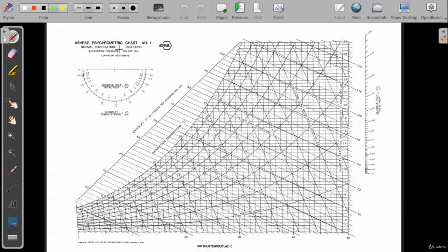Okay, so we shall use this psychrometric chart to help us retrieve the humidity ratio value. So the initial condition is 28 degrees Celsius. This is 20 all the way to 30, so 28 is over here. 28 is along this vertical line and the RH is 80%. So 80% RH is over here. The intersection point of 80% and 28 degrees Celsius will be somewhere around here. So this is the upstream condition. So maybe just label it as 0.1.